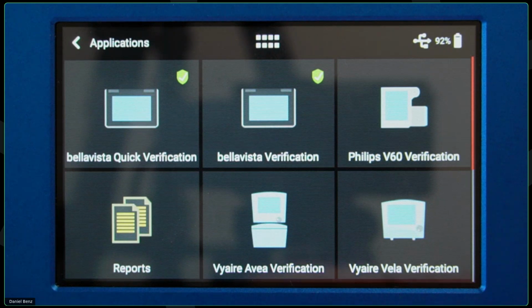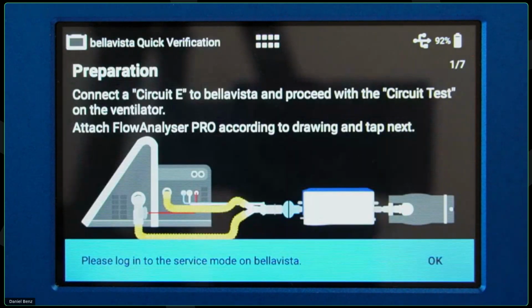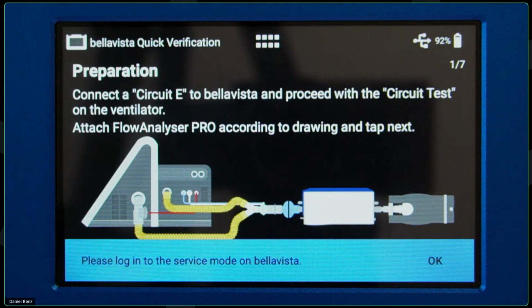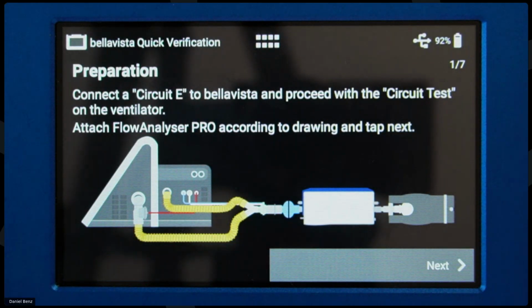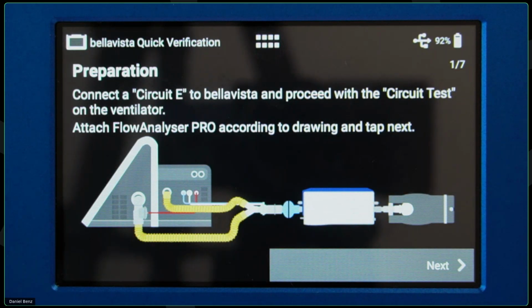So I'm going to open up this testing application, and the first thing that happens that you can't even see is the device is making all the correct settings in the background. So because we programmed this, we know what gas standard, for example, is being used by this ventilator, and we know what trigger settings work. So this is all being loaded for you automatically. And then it starts guiding me through the procedure.